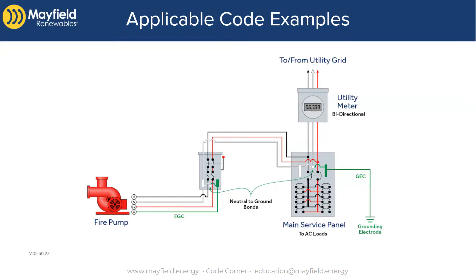Let's talk about the equipment grounding conductor — the green wire — going to the fire pump, which is absolutely necessary. But it kind of dead-ends; it doesn't continue on to a grounding electrode or back to the main service panel. Should people be doing that? I've seen AHJs adamant about it in both cases — some saying the green wire must run all the way back, others saying absolutely not. It seems to be a big sticking point.